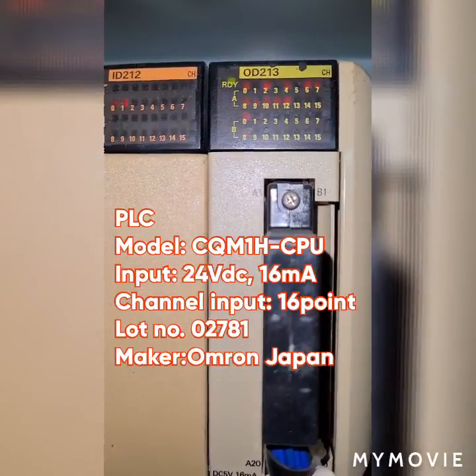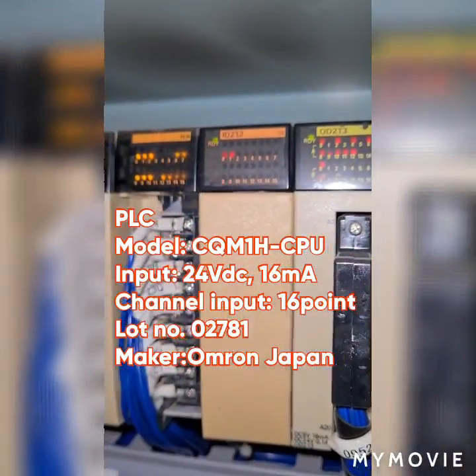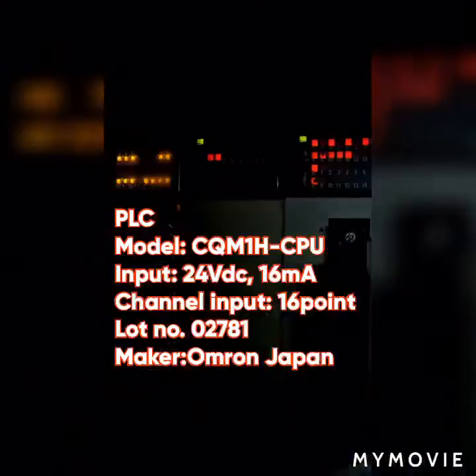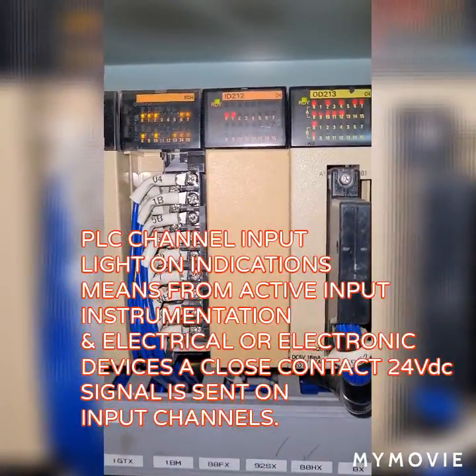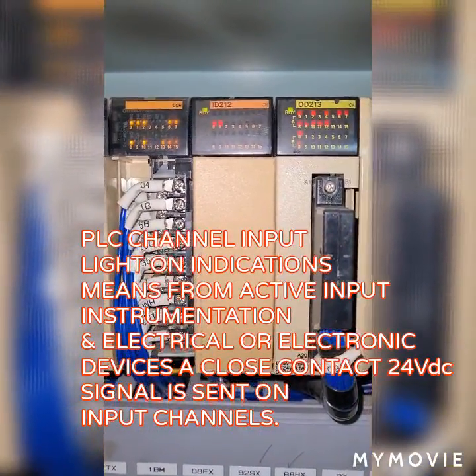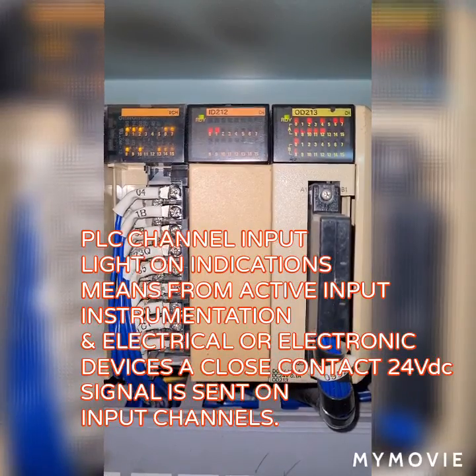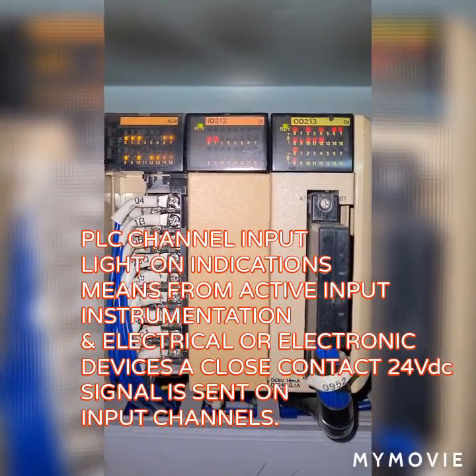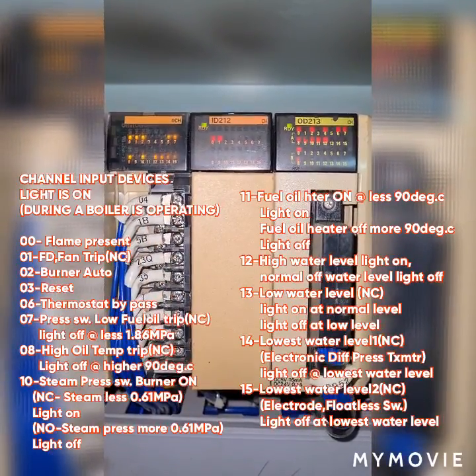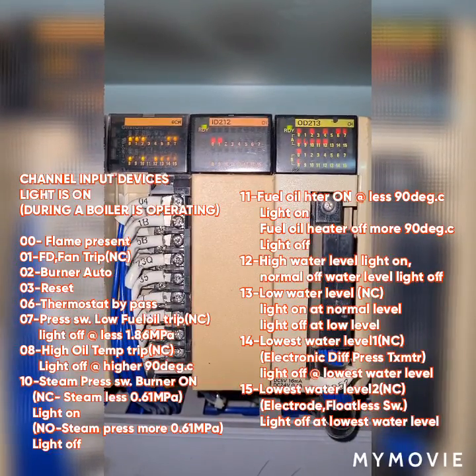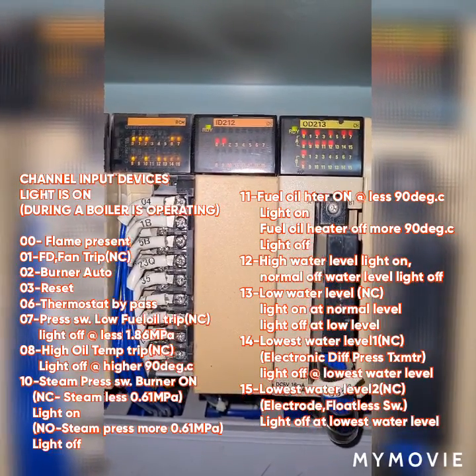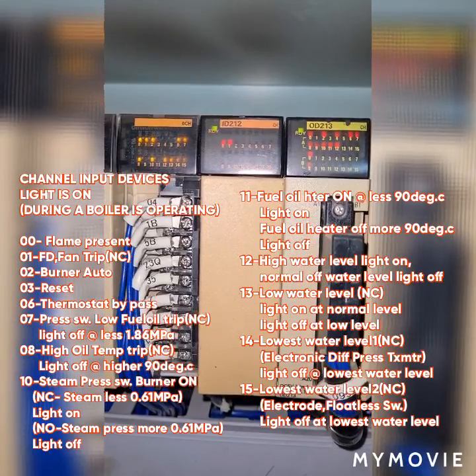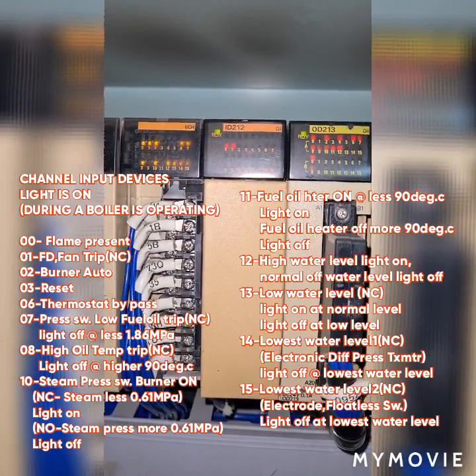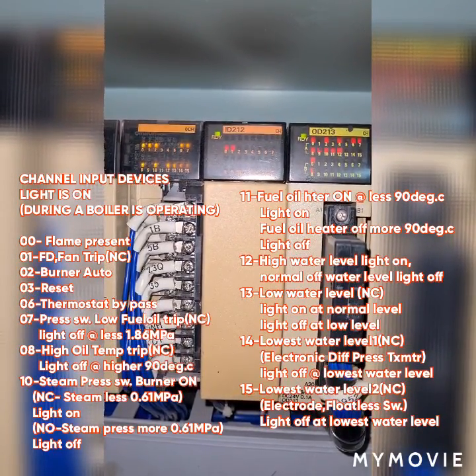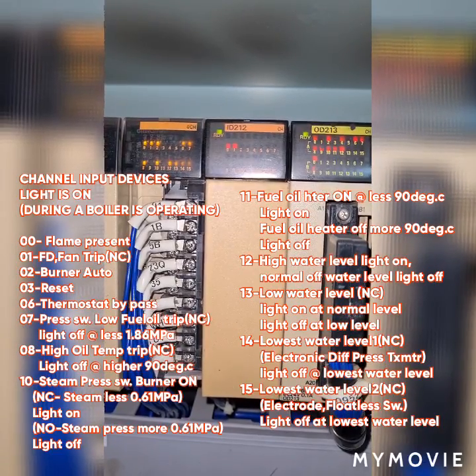Here is the PLC, model CQM1H CPU, having input of 24 volts with 16 milliamperes. Here you can see the PLC channel input lights on, indicating that the devices connected to each are active and activated. And here you can find the channel input device lights that are on while the boiler is in operation.